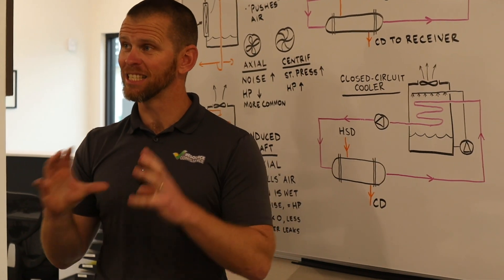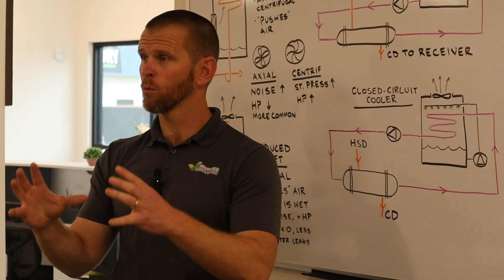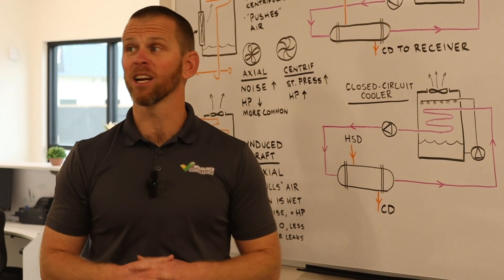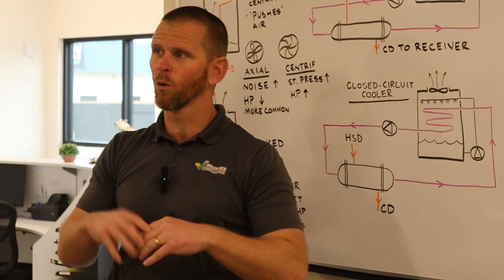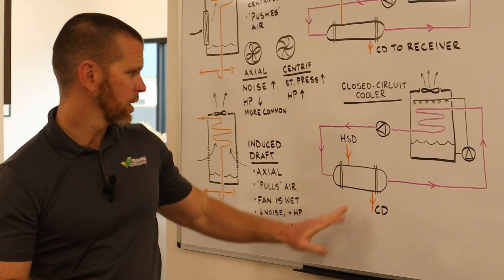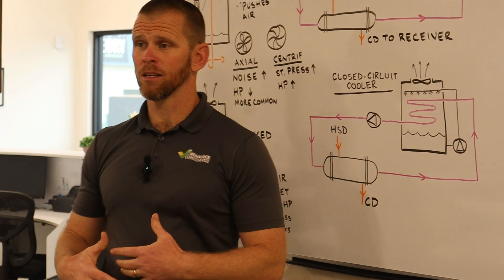You need to make sure that when you design the location where this is going to be at the plant, that there's room to physically remove the tube bundle. Because if you don't leave room, if you pack it into a corner, you're never going to be able to get access to that.